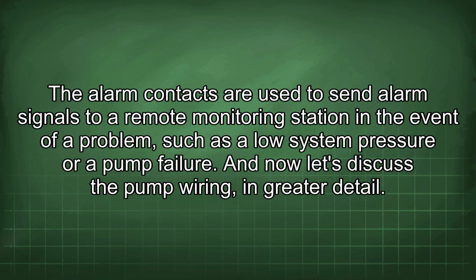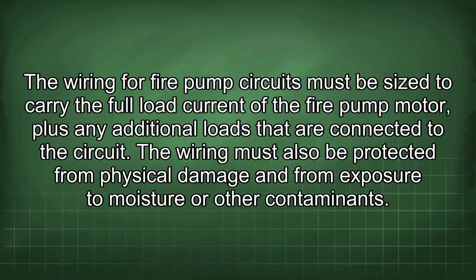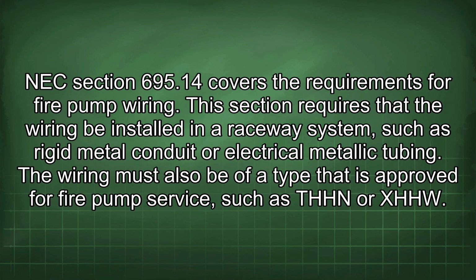And now let's discuss the pump wiring in greater detail. The wiring for fire pump circuits must be sized to carry the full load current of the fire pump motor, plus any additional loads that are connected to the circuit. The wiring must also be protected from physical damage and from exposure to moisture or other contaminants. NEC section 695.14 covers the requirements for fire pump wiring.